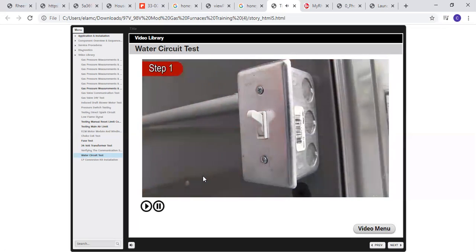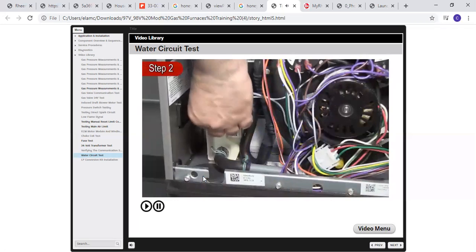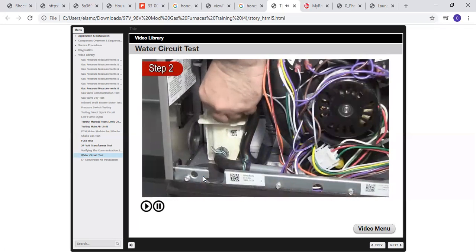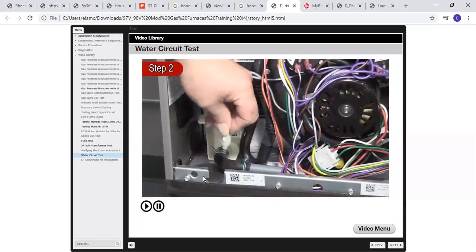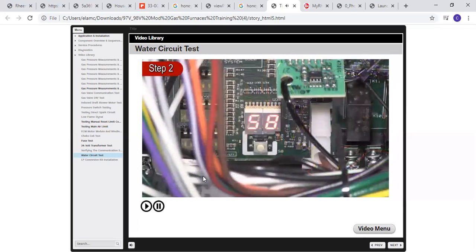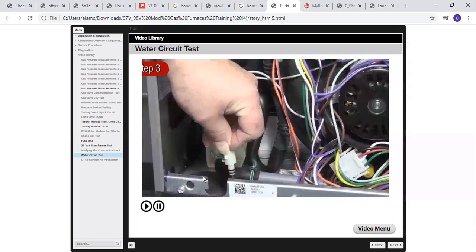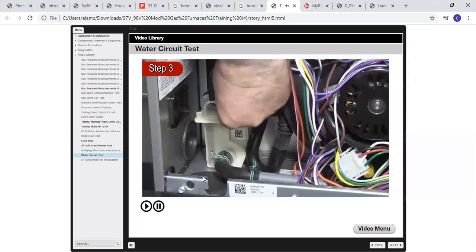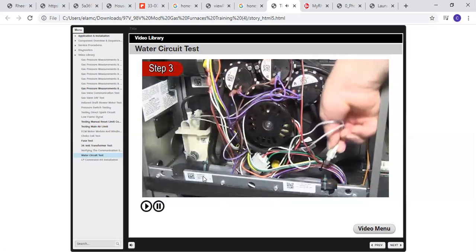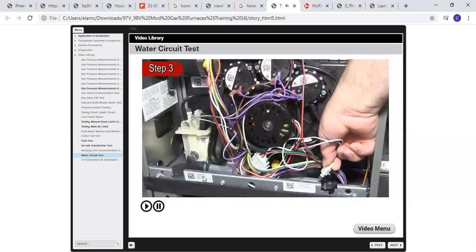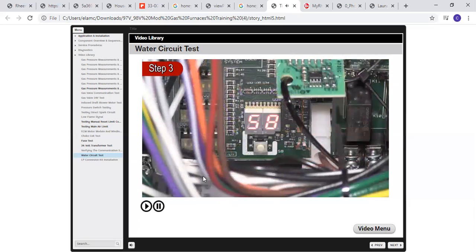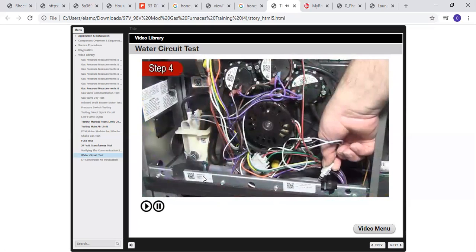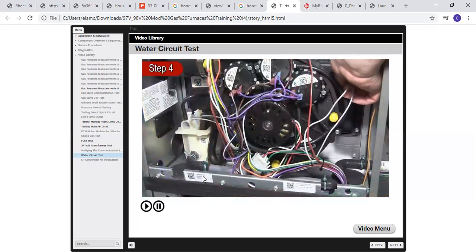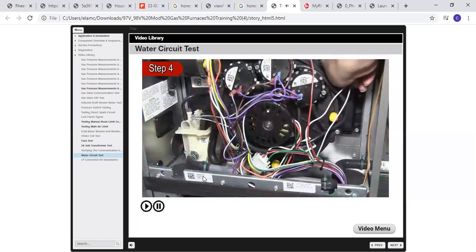Step 1. Power furnace and call for heat. Step 2. Unplug lower water sensor pin and hold the pin to chassis of the furnace. The furnace should display a code 58. Step 3. Replace the lower pin and remove the upper pin. Hold the pin to the chassis of the furnace. The furnace should display a code 58. If the furnace displays the proper code, the sensors are working properly. Step 4. Replace the top pin and place furnace into normal operation.